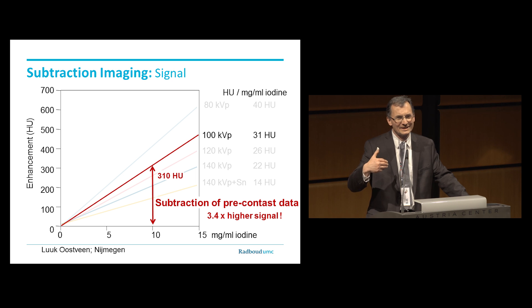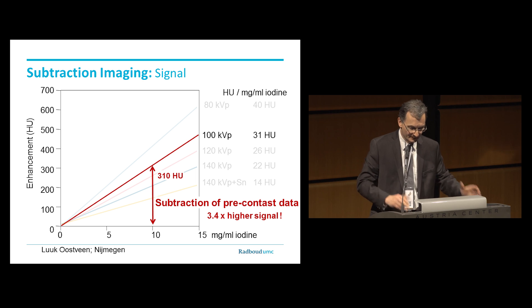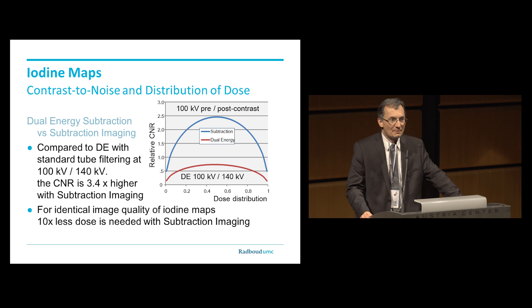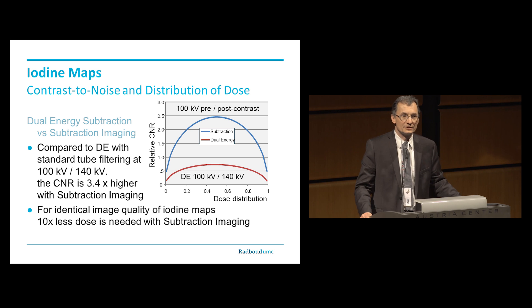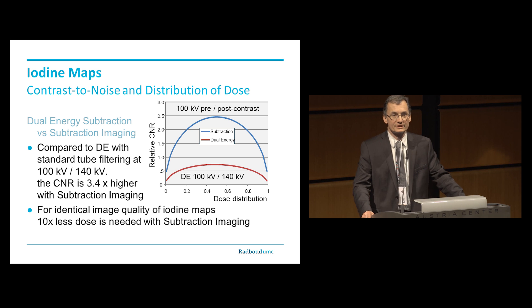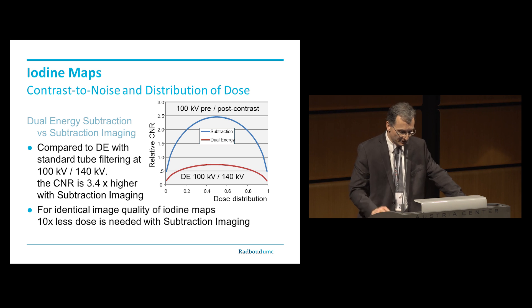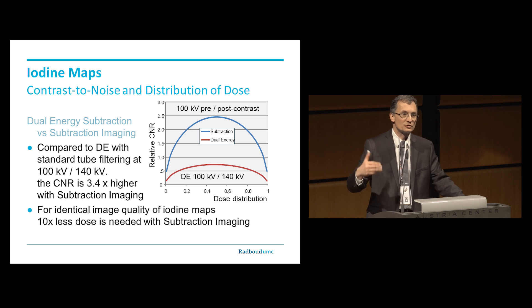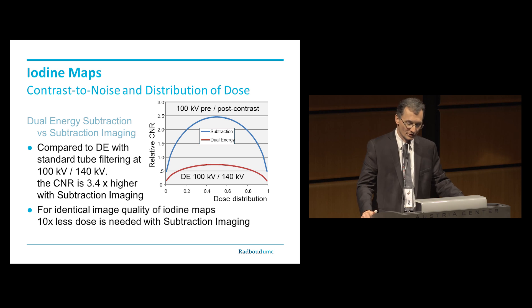If you would like to get that in terms of signal-to-noise ratio, the same amount with dual energy would have to give 10 times the dose, thanks to this square root function that relates noise and dose. Usually what happens is that the dose is not evenly distributed between the high energy and the low energy image, or in the case of subtraction between the pre-contrast and the post-contrast image. The signal-to-noise ratio is best if you have the same dose in either of the two images, because the noise in these subtracted images is always dominated by the noise in the noisier image.